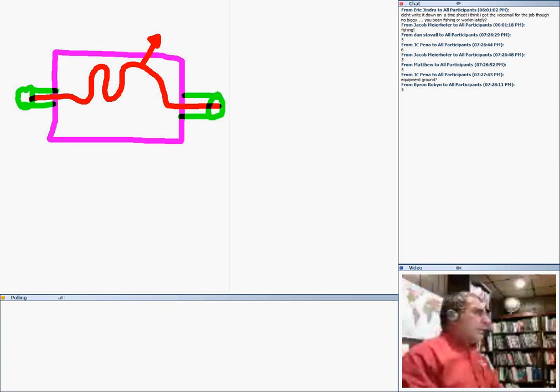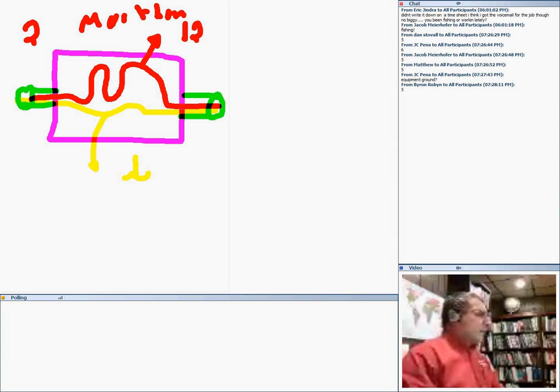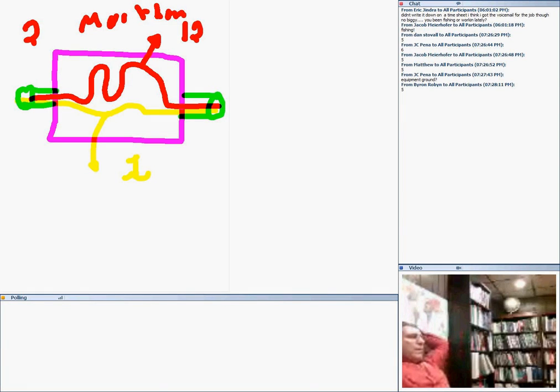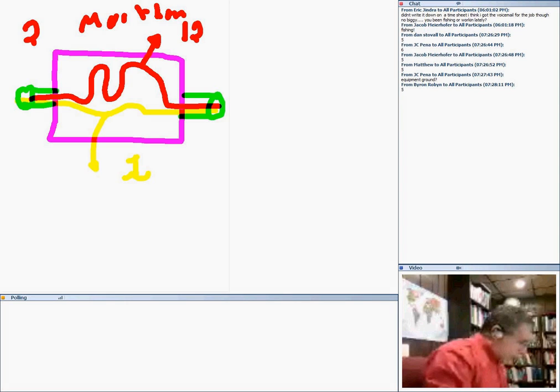The whole loop here, if it's more than 12, then this conductor counts as 2. If you put a conductor right here and you just run it straight through, this one is very important: if it's more than 12, it counts as 2; 12 or less, it counts as 1. Anything going straight through counts as 1.